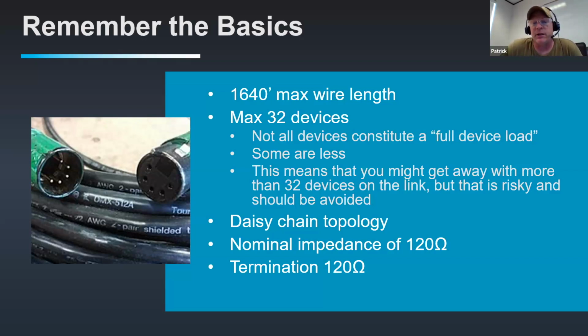So the daisy chain topology is in to out, no T's and Y's unless you're using an optosplitter. Cable of the proper impedance is hard to come by otherwise. On the left-hand side of the picture, DMX512A is stamped right on the cable, so you know it's the right twist, the right capacitance, and the right gauge. And then there's your 120 ohm resistor terminator that you put on the end of the line, especially if you're using RDM.